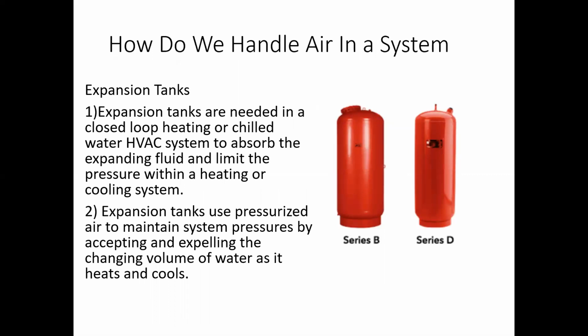So how do we handle air in a system? Now we're talking about pressure, right? We're talking expansion. And when you look at that, you really need an expansion tank, because that water is heating up and cooling down, and you're having that contraction and expansion of the water. You need it to go somewhere. So expansion tanks are needed in a closed loop heating or chilled water system to absorb expanding fluid and limit the pressure within the system. And expansion tanks use pressurized air to maintain system pressures by accepting and expelling the changing volume of the water as it heats and cools. So you need it to go somewhere, right? That's what the expansion tank is.